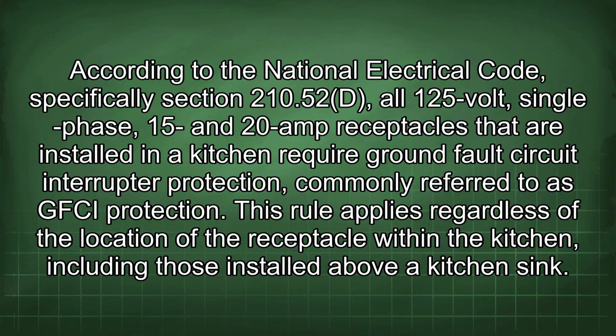According to the National Electrical Code, specifically Section 210.52(D), all 125-volt single-phase 15 and 20 amp receptacles that are installed in a kitchen require ground fault circuit interrupter protection, commonly referred to as GFCI protection. This rule applies regardless of the location of the receptacle within the kitchen, including those installed above a kitchen sink.